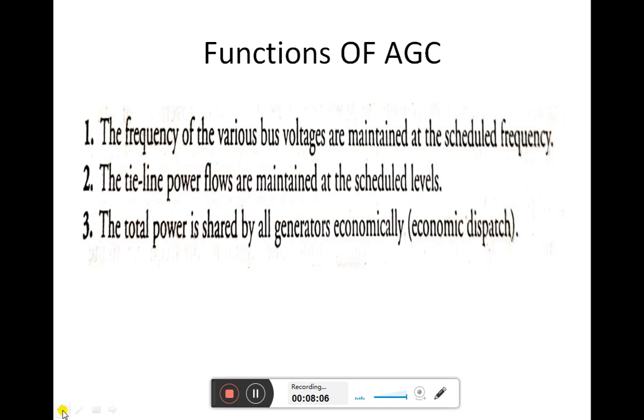As the frequency decreases, the power taken by load also decreases. Equilibrium in a larger system is generally obtained when the reduction in frequency sensitive load balances the output of the tripped generator or the load increase at the new frequency.